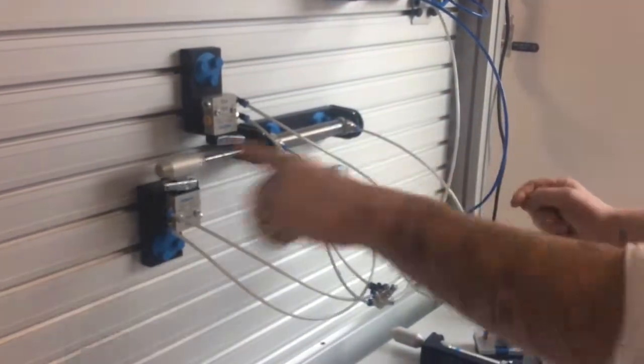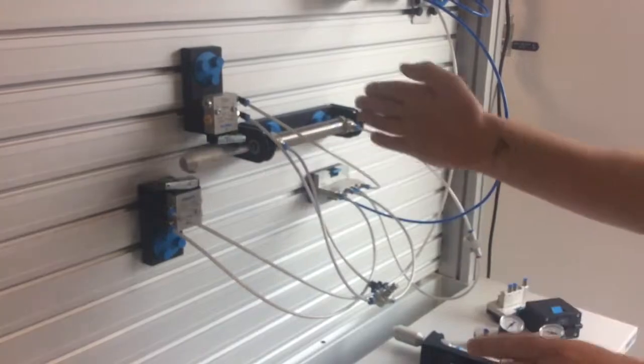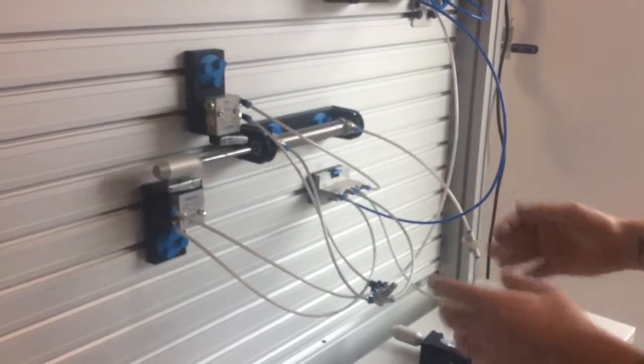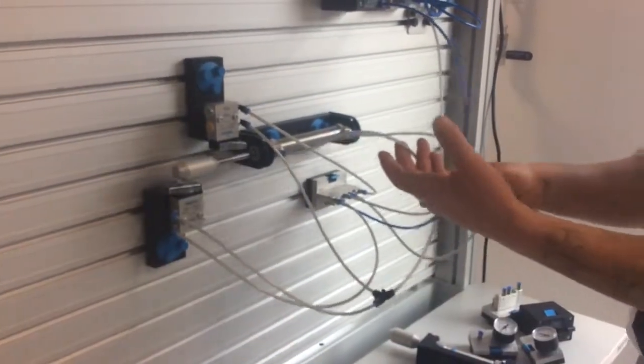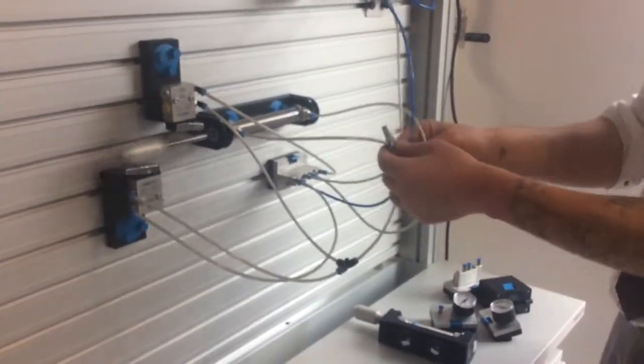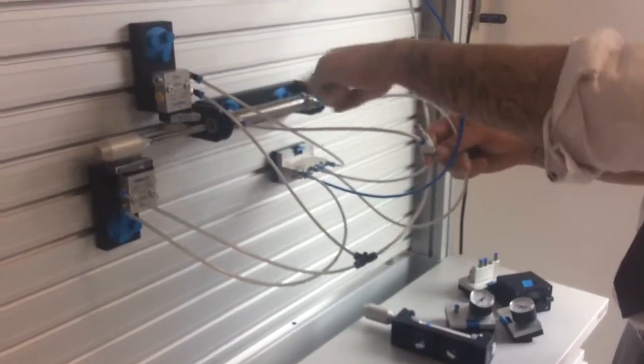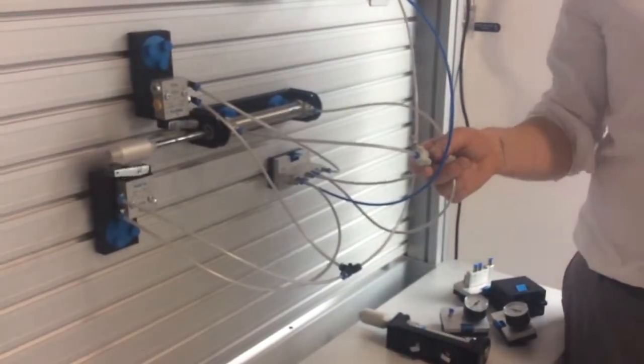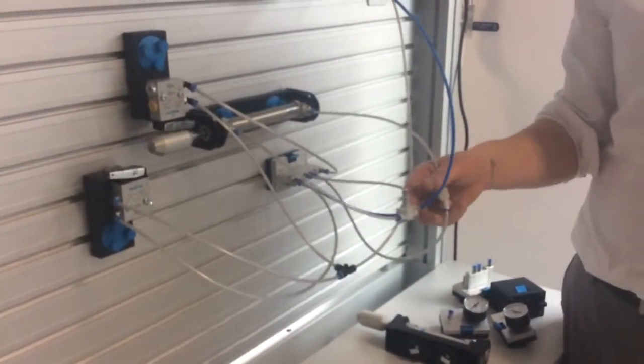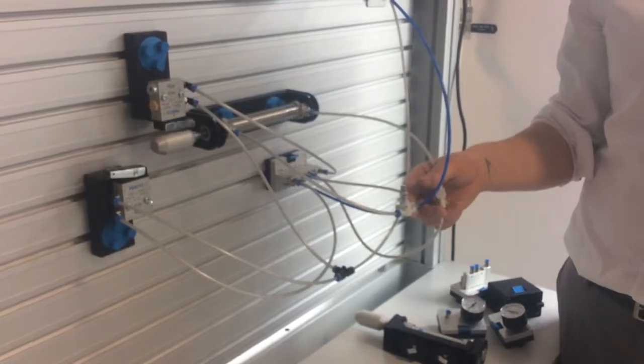Now, you'll notice that the cylinder is extending and retracting quite slowly, under full pressure. This is because we have flow restrictors on both lines into it. So we can control the speed out, and we can control the speed in.